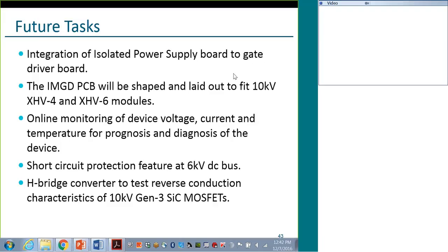Yes. So right now, where we are in terms of validating this, we have seen a reduction in losses by around 10 to 15% from a normal gate driver with active gating. But I must mention that the loss reduction is one aspect. The reason we are going into the medium voltage intelligent gate driver is because we actually want to turn this gate driver into a diagnostics and prognostics unit, which looks at the health of the device.